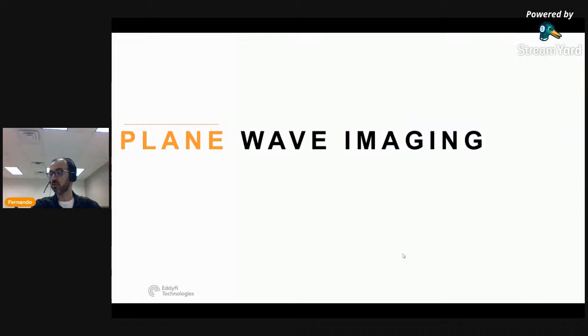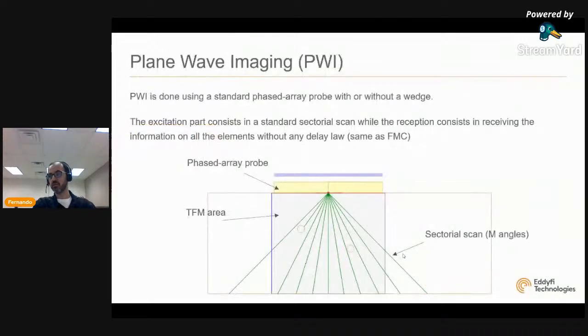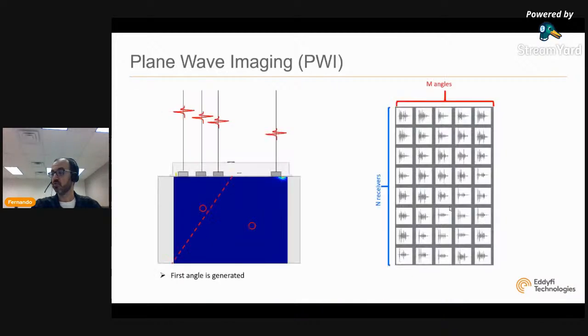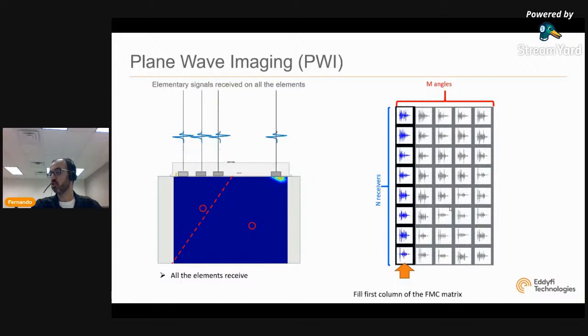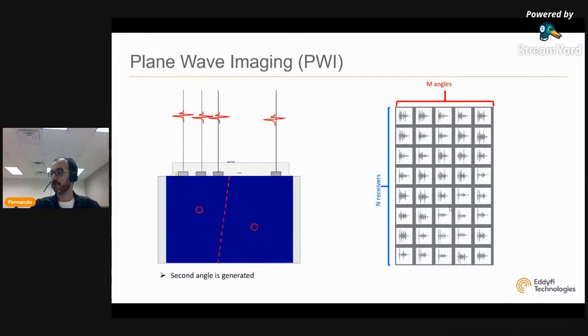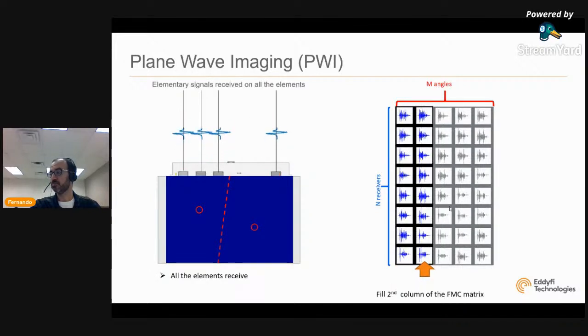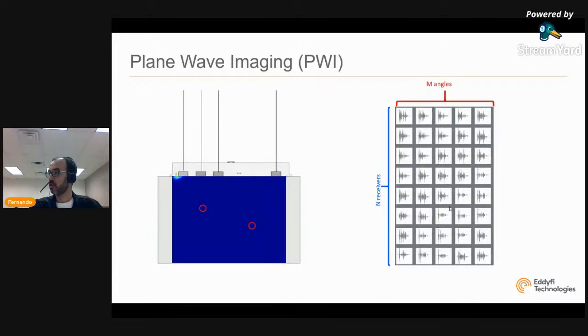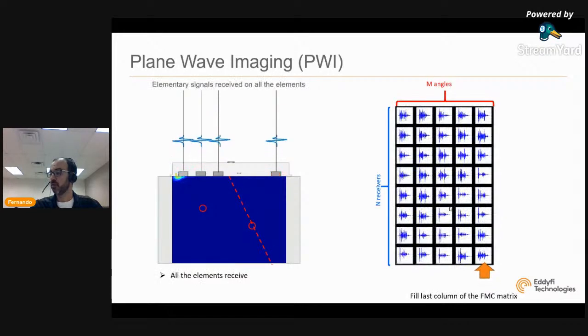We also have another technology called plane wave imaging. Imagine phased array where you're pulsing all the elements and receiving. In this case, you pulse with a certain amount of elements and you receive with all the elements. It's pretty much like a sectoral scan. In this case, we'll say it fires 8 or 16 elements at one angle, sends, receives, then switches to another angle, sends, and receives the information back to the transducer. It sends again, depending on how many angles you have.